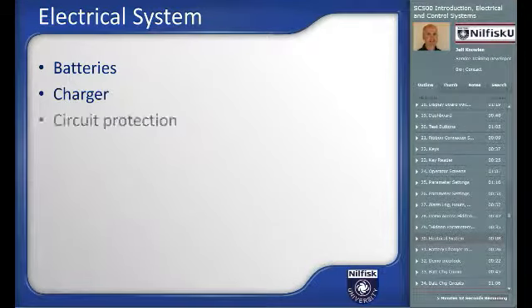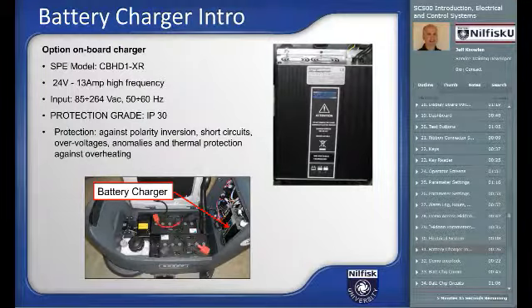The electrical system consists of the foundational items like the batteries, the battery charger, and circuit protection. An optional onboard battery charger is available. It is an SPE model CBHD1-XR. It is capable of receiving power sources from 85 to 264 volts AC and 50 to 60 Hertz, so it can be used in many different markets. It has built-in protection for polarity inversion, short circuits, overvoltages, and thermal protection against overheating.